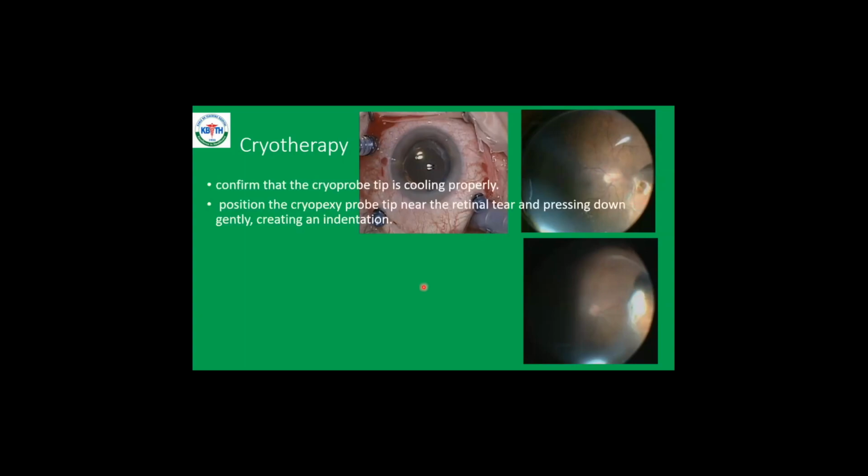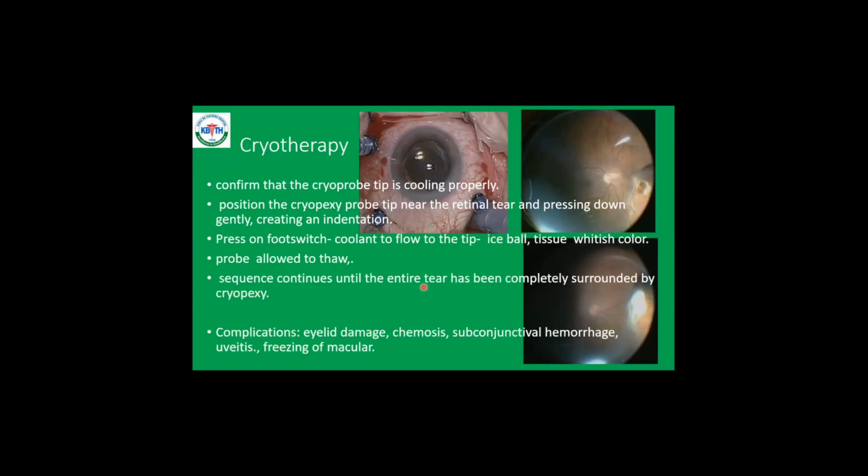But first of all, you need to know that cryoprobes tend to be very unreliable, and you should confirm that it is working and cooling properly before you use it. It can also lead to some complication.